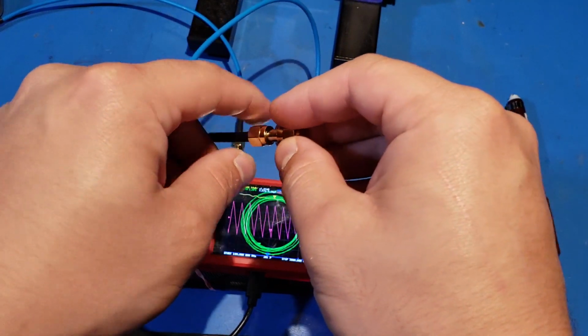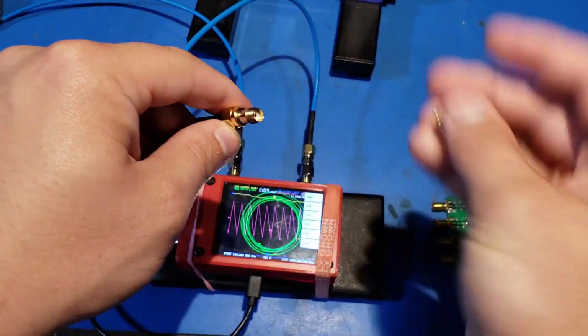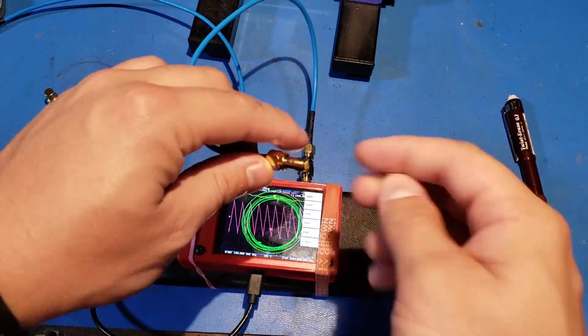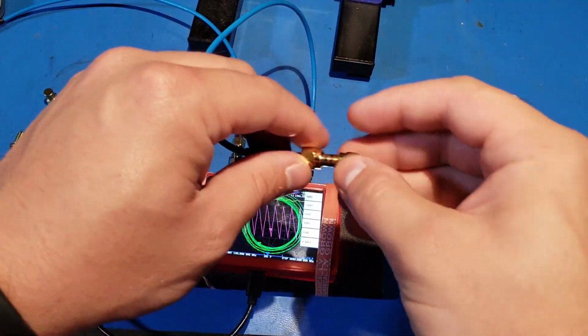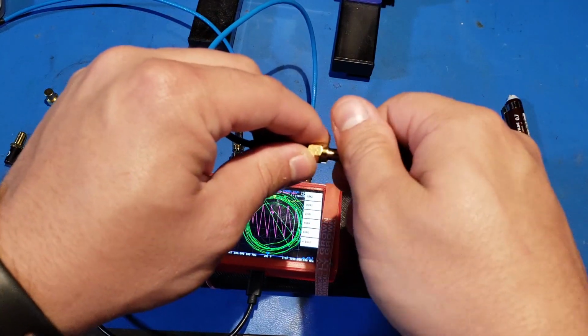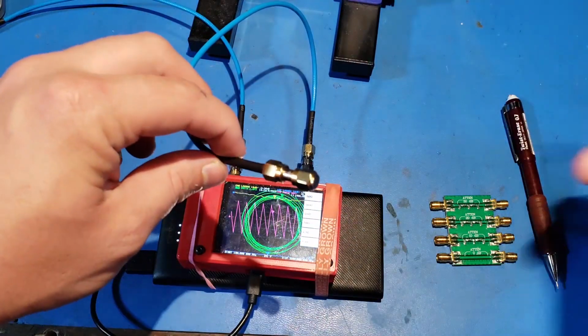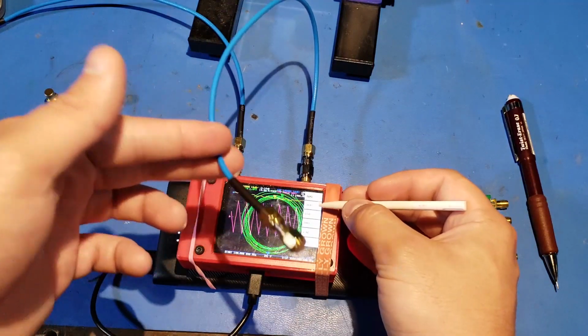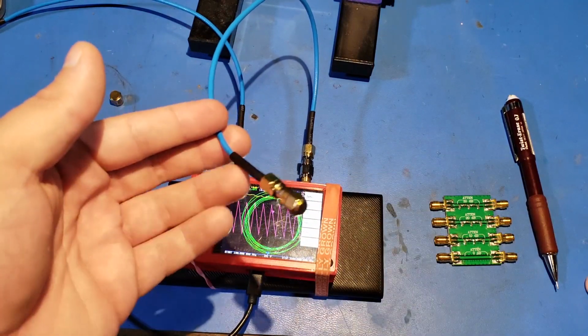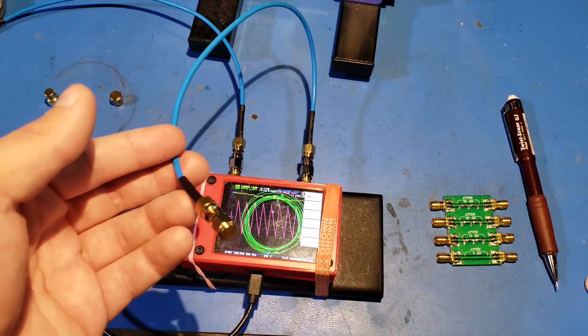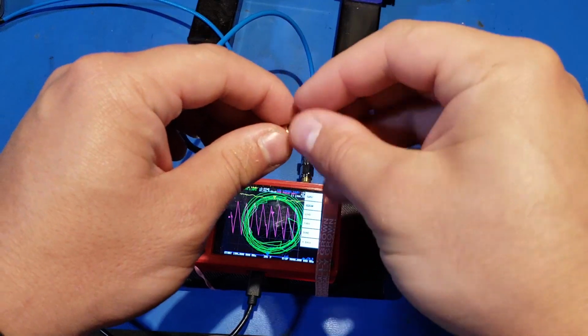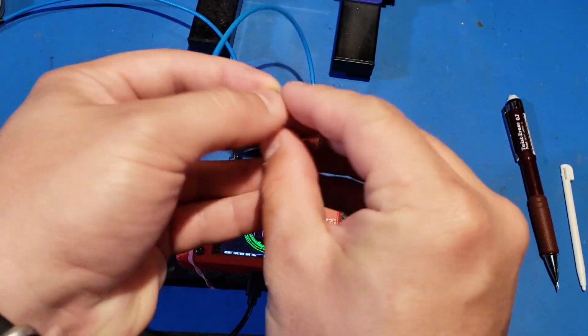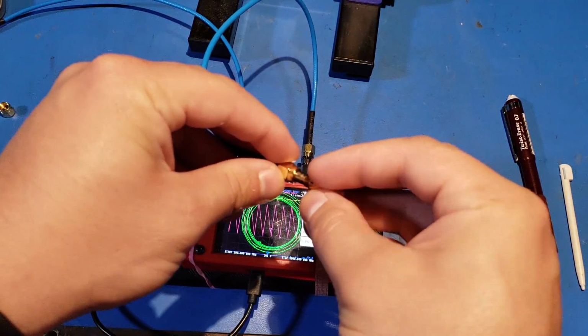Once that finishes, we disconnect the open standard. You want to make sure that you have the connector in there snug so that when you go to disconnect the open standard, it doesn't start spinning that female-to-female SMA adapter in there. Otherwise, you have to be careful disconnecting it to not spin around the center pin there. Next is our short standard, which has the pin in it, unlike the open standard, even though they otherwise look identical. See, they had the pin in it. And then next is our load standard.